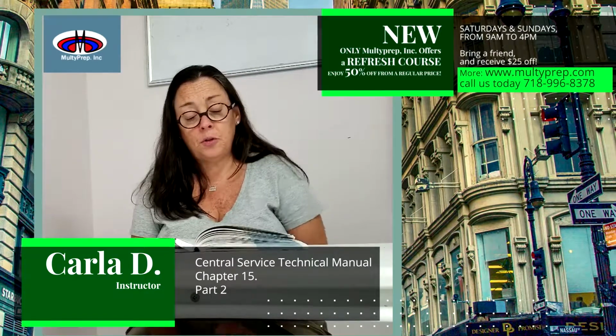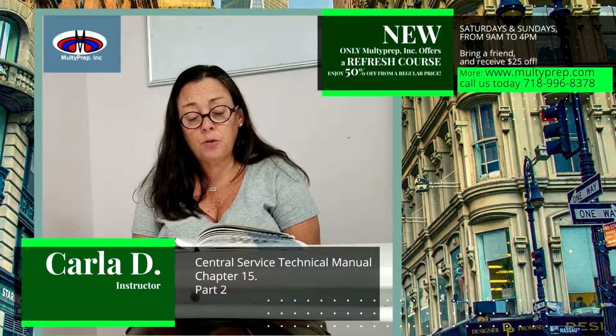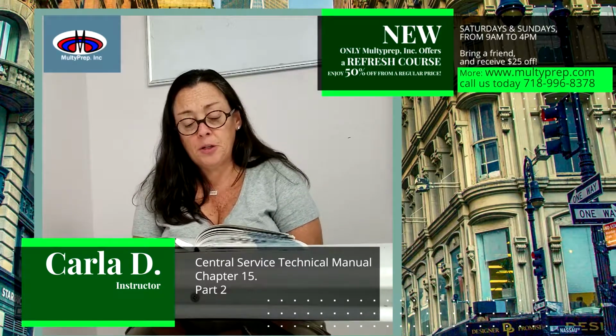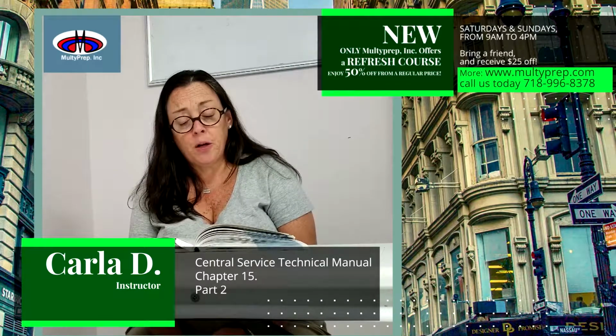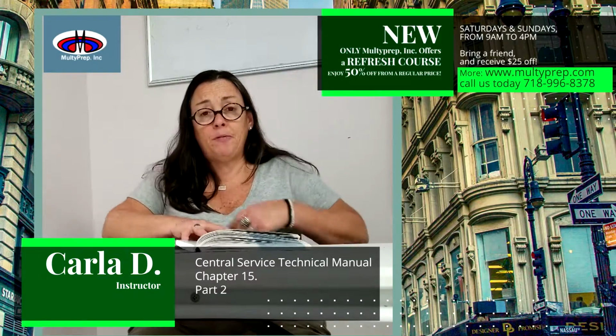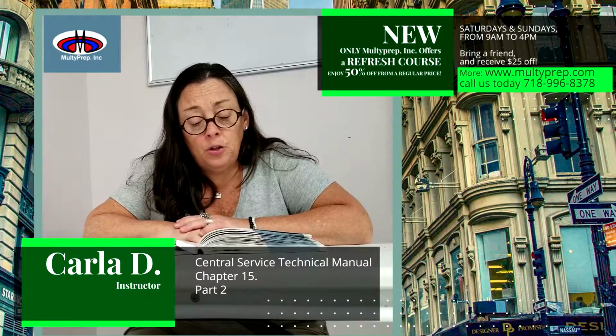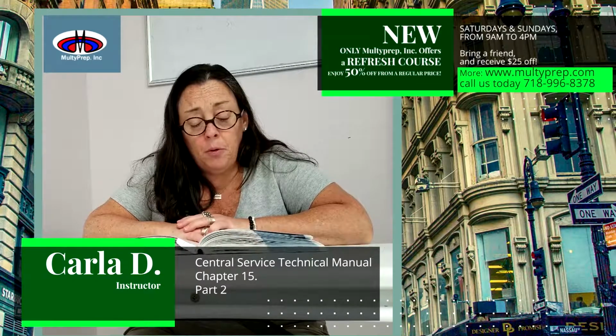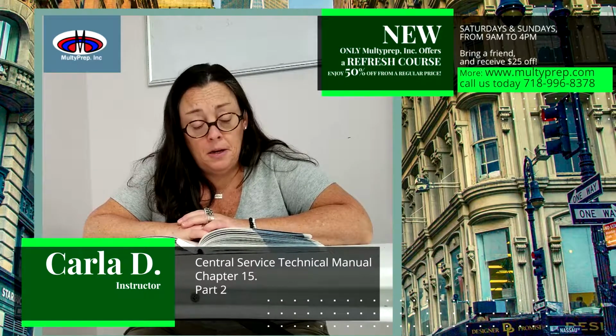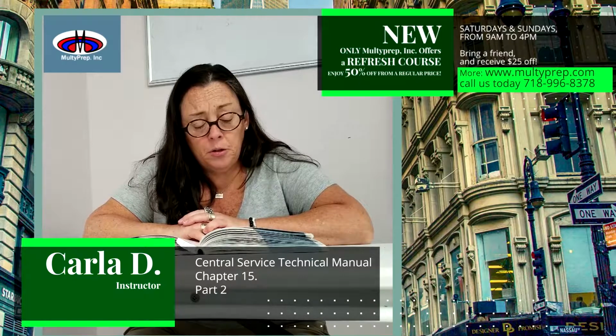To minimize the likelihood of exposure to hydrogen peroxide when removing items from a canceled cycle, CS technicians should always wear vinyl, PVC, or nitrile gloves, never latex. As with any chemical used for sterilization, healthcare workers should consult the safety data sheets and follow all manufacturers' recommendations and departmental procedures. To minimize hydrogen peroxide risks, employees should be instructed about the following: hazards of hydrogen peroxide, storage, handling, and disposal of hydrogen peroxide cassettes, handling canceled cycles, applicable OSHA standards, the use of PPE, applicable SDS, safety data sheets, and recommendations for routine maintenance of sterilization equipment.